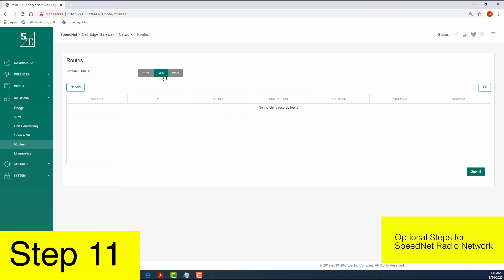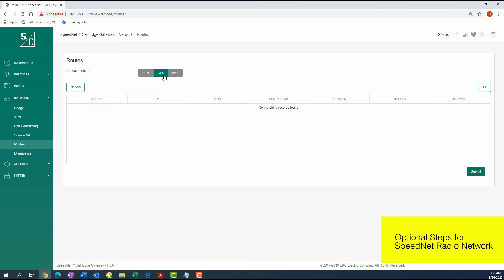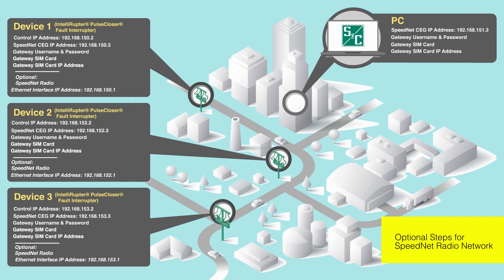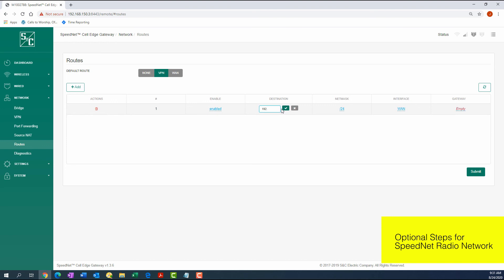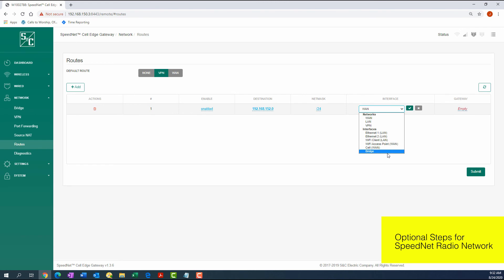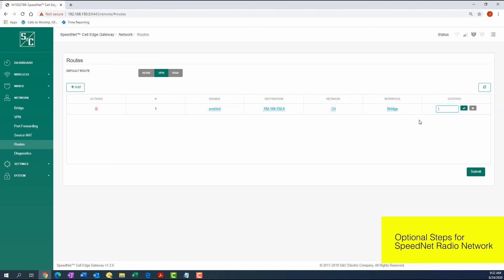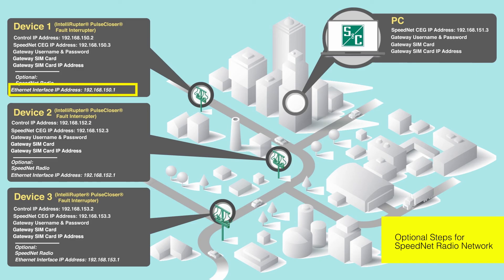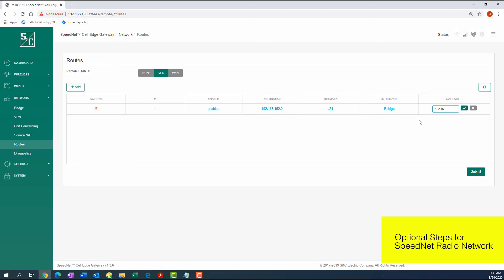Step 11: Add a route for each Speednet radio on the private wireless network that is remote from the gateway by completing the following. A: Click the Add button to start a new route. B: In the Destination column for the route, enter the IP address for the subnet that traffic on the Speednet radio network should reach and accept by clicking the green box. Note that the destination setting must be compatible with the NetMask setting for the route. C: Change the Interface setting to Bridge. D: In the Gateway column, enter the IP address of the radio that will transmit traffic over the private wireless network. Click Submit to accept the changes.